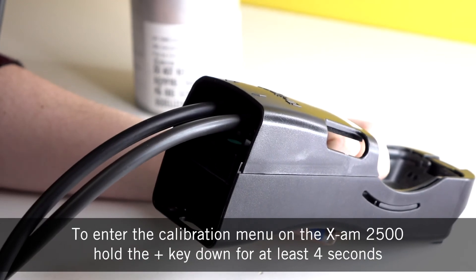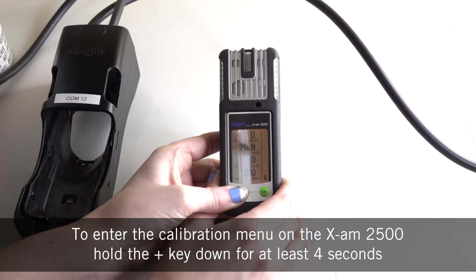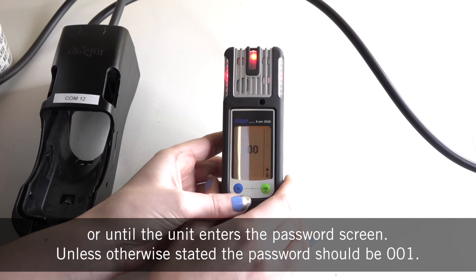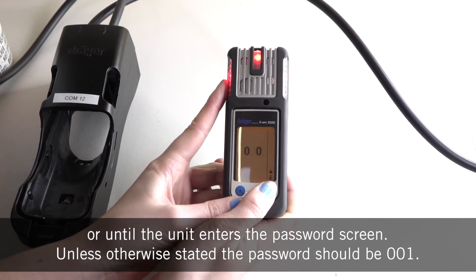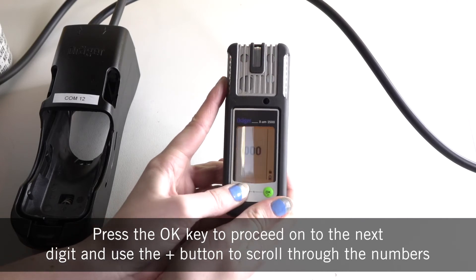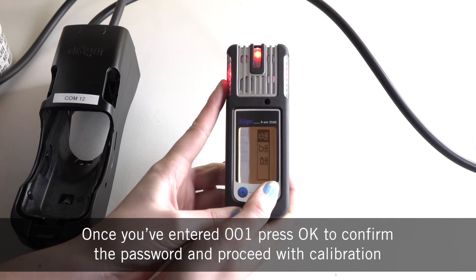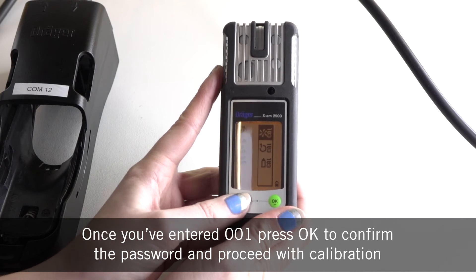To enter the calibration menu on the X-am 2500, hold the plus key down for at least 4 seconds or until the unit enters the password screen. Unless otherwise stated the password should be 001. Press the OK key to proceed onto the next digit and use the plus button to scroll through the numbers. Once you've entered 001, press OK to confirm the password and proceed with calibration.